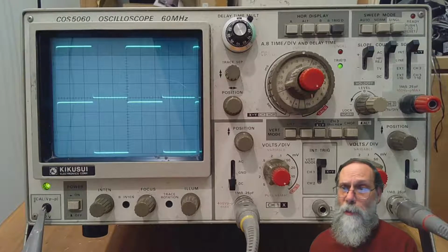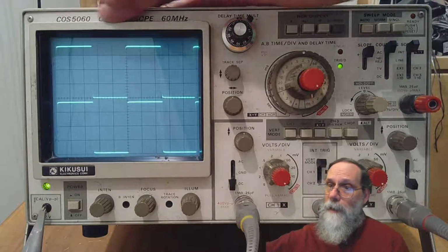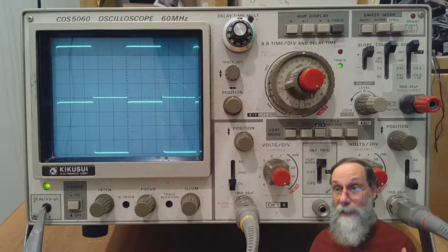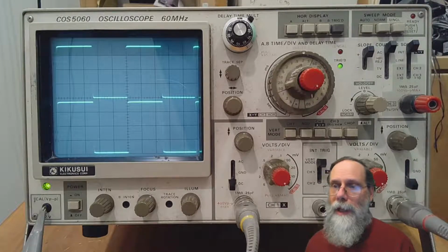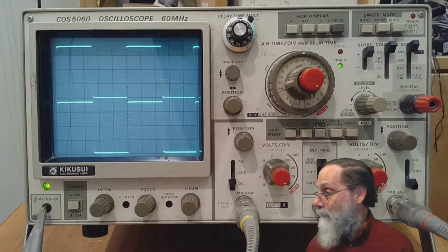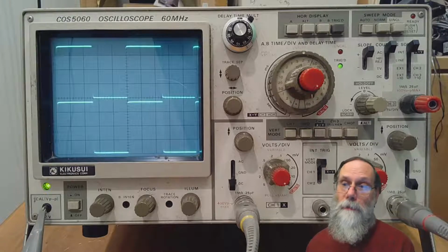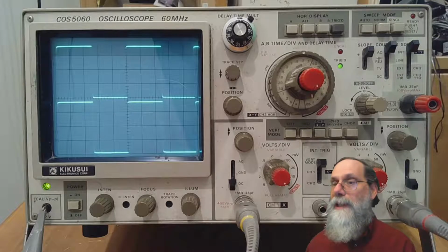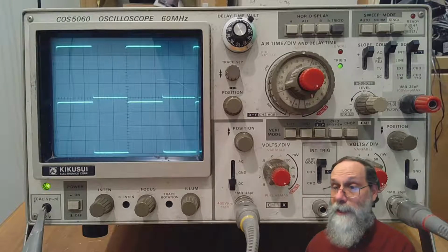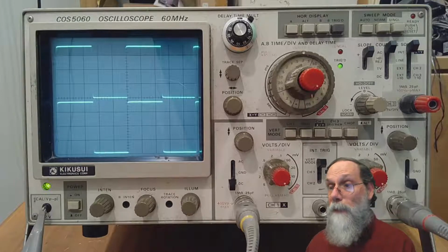The way an analog oscilloscope works is that there's a phosphor screen here, on a vacuum tube. And that vacuum tube actually runs the entire length of this box. What the vacuum tube is doing is shooting an electron beam at the phosphorescent screen, and where the beam hits the screen, it causes light to be emitted. And it's sweeping the beam across the screen from left to right, according to some time base. Basically just using a ramp waveform and some plates to set up an electric field to deflect the beam. It's got another set of plates to deflect the beam vertically.